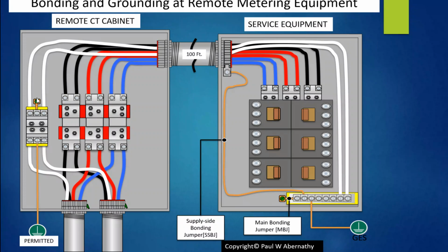This is a factory installed jumper here, supply side bonding jumper. So it is done and it already takes the place. If it was a wire, then we're going to size it based on the size of these conductors, and we've already gone over that. Here would be this one and this one added together. That's the size it's going to be. And you go to 250.102C1 and you're going to do that. Now, here's the permitted grounding electrode system, okay? Here's the required one over here, okay? And it's connected to the grounded conductor, which is connected here to the enclosure, brings everything together here, all right?